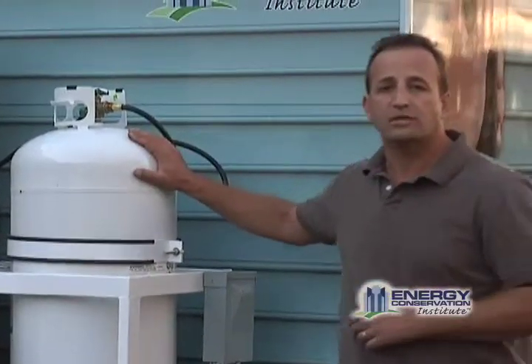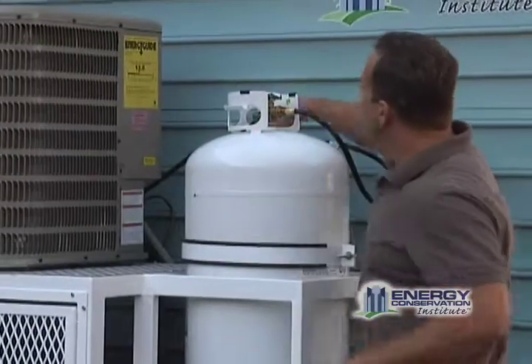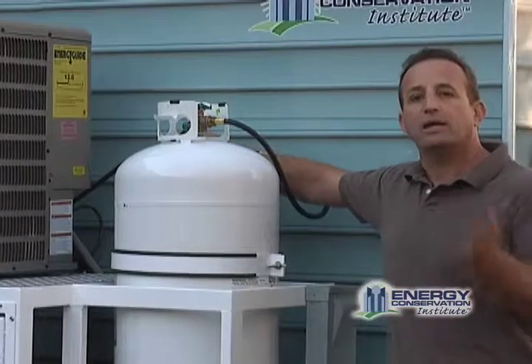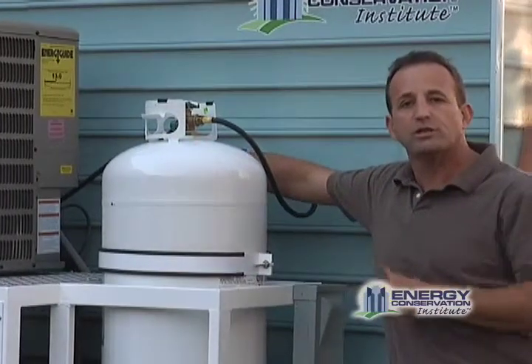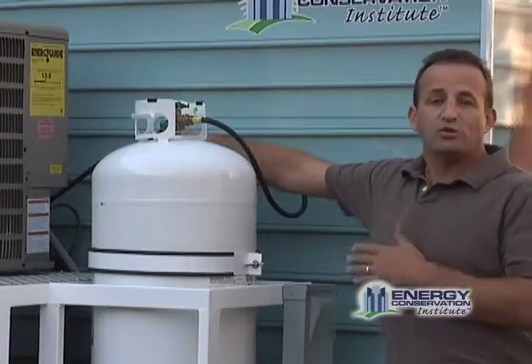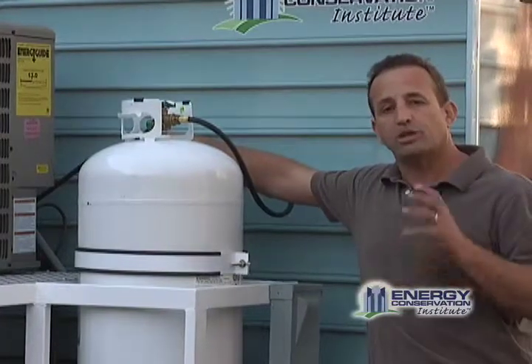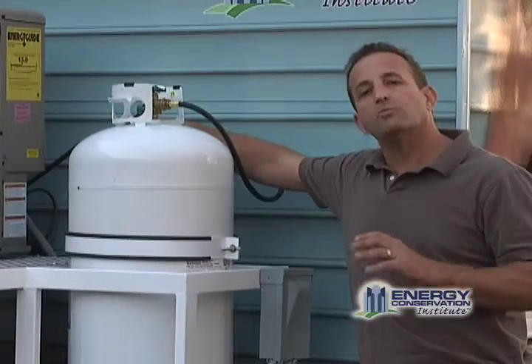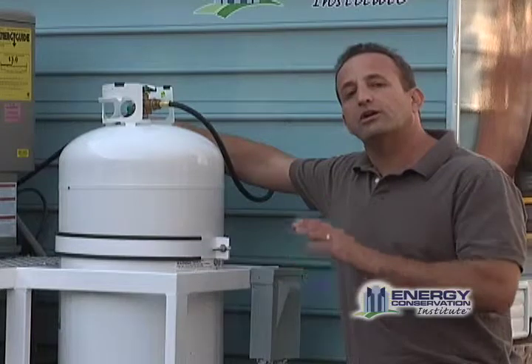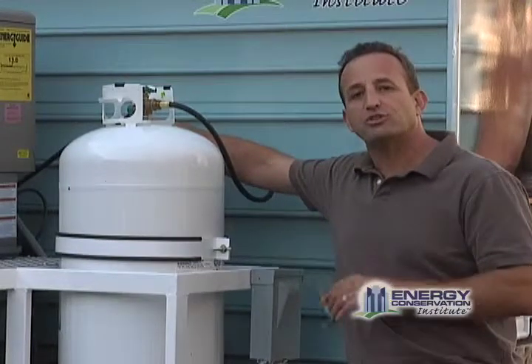When one of these tanks runs empty, you have a switch up here on the valve that will allow you to automatically switch over to the other one just by turning the knob here. Also mounted on this valve is our pressure control system, which keeps the propane pressure going to the generator and to the appliances at the manufacturer's recommended level.